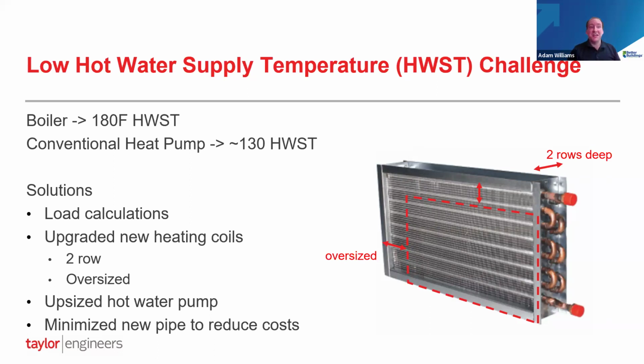Also, traditionally the cost differential between, say, a 1 million BTU boiler and a 1.5 million BTU boiler is not that much, relatively speaking. So I don't think as much risk was taken in trying to right size heating systems. Whereas now the size and the cost associated with this equipment very much matters. So we really try hard to right size and do load calculations to get the right size heating system. Half of it is doing that, and half of it is convincing an owner, especially on an existing building where they might have comfort problems, that your heating system is oversized. We want to provide a smaller size heating system. That can be a hard conversation to have, but it is worth having to try to make this work affordably.